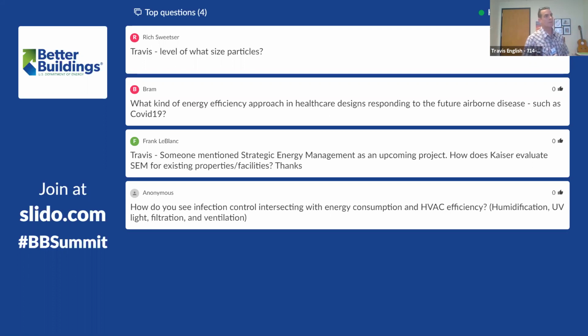In the experiment we did in patient rooms, we used PM1 plus sensors, which were cheap, and we could deploy 70 of them throughout the building, comparing to outside air. We found that even at 1.5 air changes or 1 air change, your indoor particle counts are 10% of your outdoor particle counts or less. It's very, very clean inside the hospital building when you're downstream of those filters.